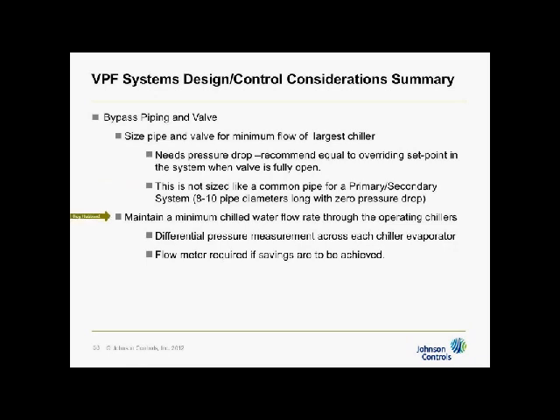What it does is, as we said, maintain minimum chilled water flow through operating chillers. It can be done one of two possible ways. Flow meter is preferred. I'm going to mention it first because it's much more accurate, and I can get closer to the minimum flow of the chiller than I can with a pressure sensor. The differential pressure sensor has the negative point. I have 20 feet of pressure drop at 3,000 GPM through these chillers. If I go down to minimum flow, which for these chillers is 776 GPM or just about 25% flow, then it's 0.25 squared. 0.25 squared is 0.0625 times my 20 feet, which means I'm at 1.2 feet.